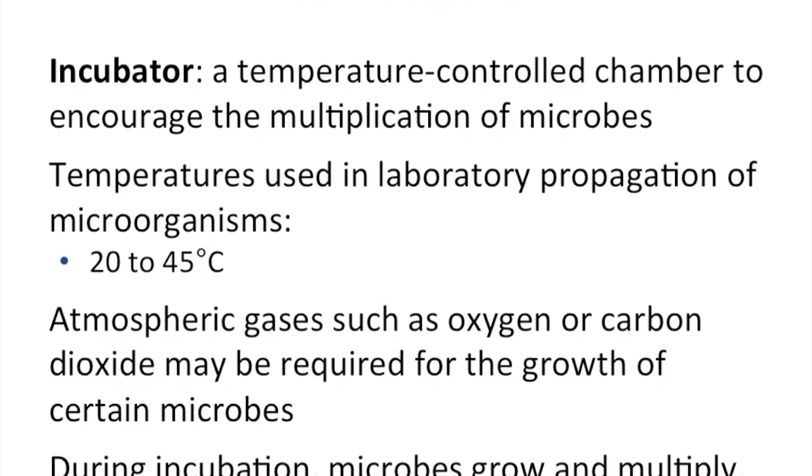The temperature normally is from 20 degrees to 45 degrees Celsius. So the incubator can adjust these temperatures. We can also adjust the oxygen or carbon dioxide concentration in the atmospheric environment in the incubator to provide the optimal condition for the microorganism to grow.